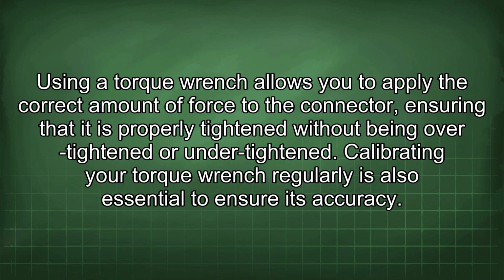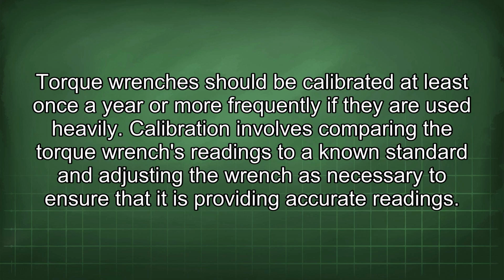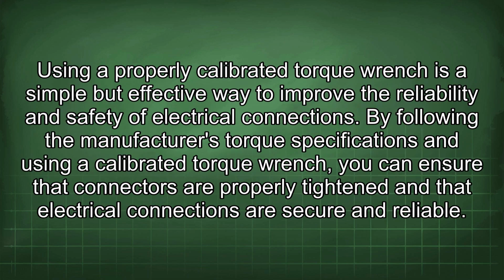Using a torque wrench allows you to apply the correct amount of force to the connector, ensuring that it is properly tightened without being over-tightened or under-tightened. Calibrating your torque wrench regularly is also essential to ensure its accuracy. Torque wrenches should be calibrated at least once a year or more frequently if they are used heavily. Calibration involves comparing the torque wrench's readings to a known standard and adjusting the wrench as necessary to ensure that it is providing accurate readings. Using a properly calibrated torque wrench is a simple but effective way to improve the reliability and safety of electrical connections. By following the manufacturer's torque specifications and using a calibrated torque wrench, you can ensure that connectors are properly tightened and that electrical connections are secure and reliable.